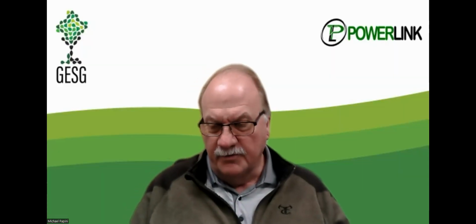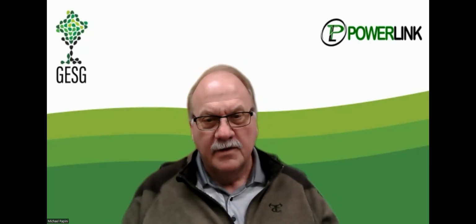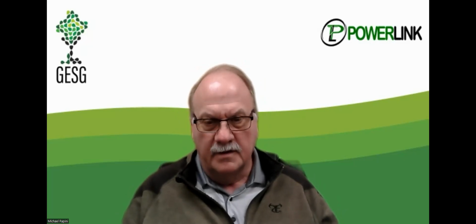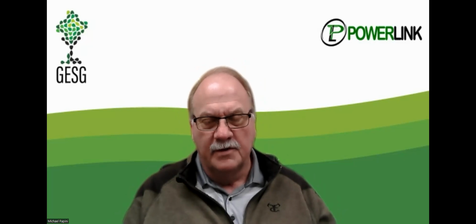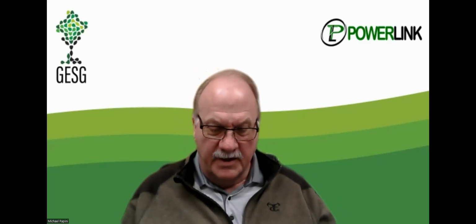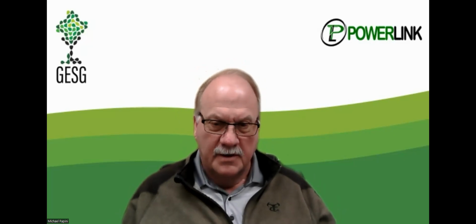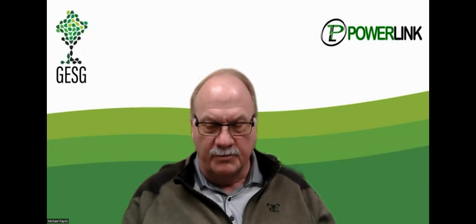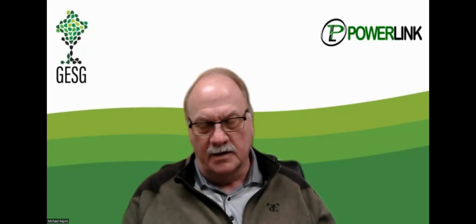And so that was kind of an interesting discovery, because what we would think would be horribly inefficient really wasn't, and what we thought would be fairly good wasn't. It's the opposite. Yeah. Usually those motors are on VFDs, so they become really efficient, above 0.9, because they dial down the hertz on a VFD, a variable frequency drive. What that does is keep the water pressure at certain levels, so you're not running the water pressure at full all the time. It's kind of like a dimmer switch.